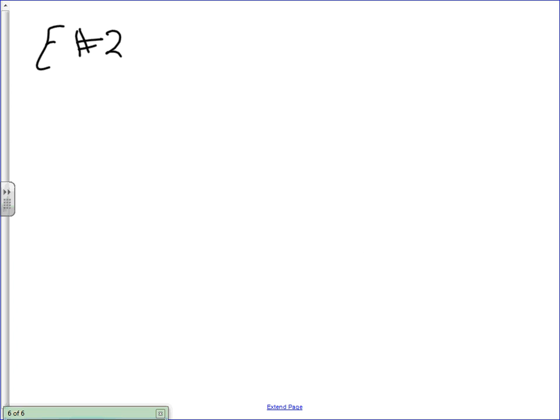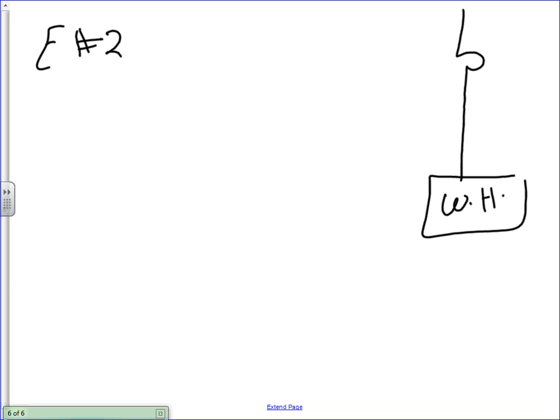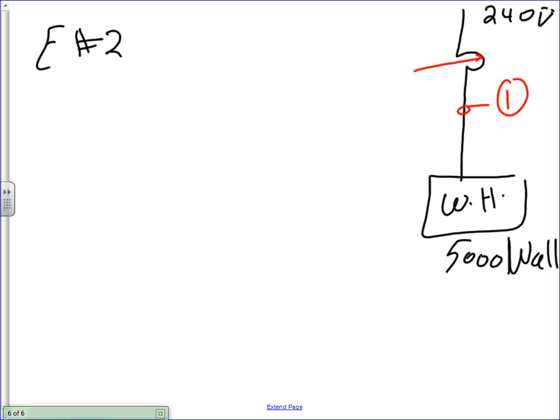Example number 2. Now here's one example. I have an overcurrent protection device, and I have a water heater, and my water heater is 5,000 watt. A 5,000 watt water heater. The voltage system is 240 volt. And I need to size the following for this boy. I need to size number 1, conductor. Number 2, overcurrent protection device. Conductor and overcurrent protection device.